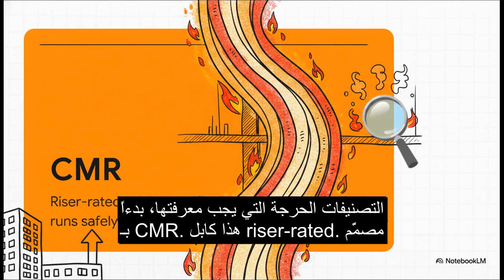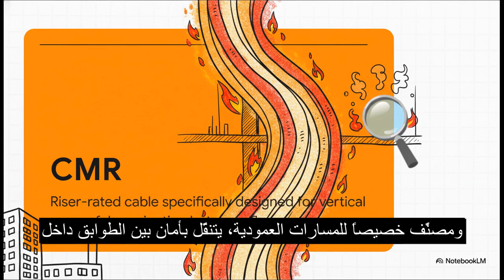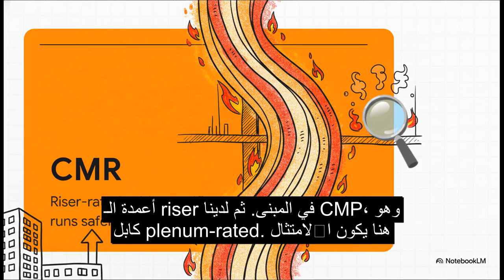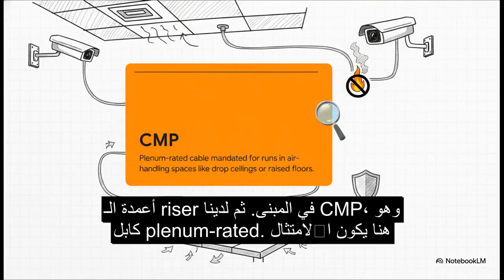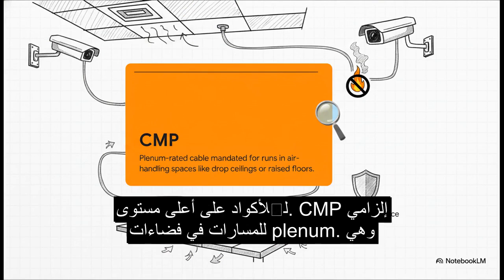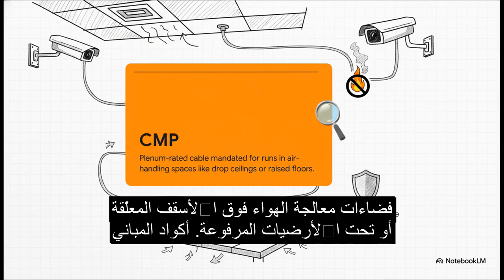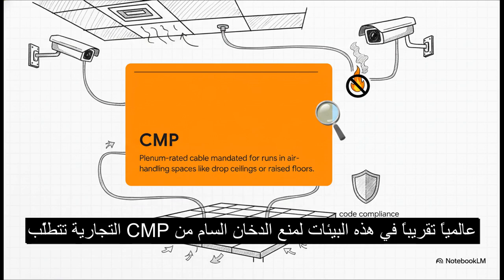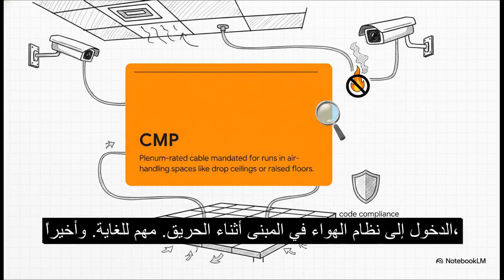with CMR. This is your riser-rated cable. It is specifically built and rated for vertical runs, safely navigating between floors right inside a building's riser shafts. Then we have CMP, which is plenum-rated cable. This is where your code compliance really kicks into high gear. CMP is mandated for runs in plenum spaces. Those are the air handling spaces you find above dropped ceilings or beneath raised floors. Commercial building codes almost universally require CMP in these specific environments to prevent toxic smoke from entering the building's air supply during a fire. It's incredibly important.